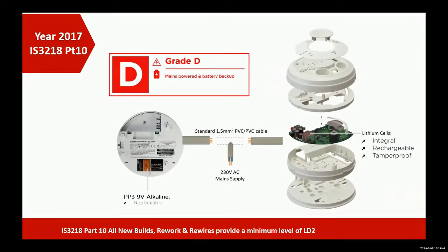So again, going back, we didn't change anything on the grade of system. The grade would still remain mains powered with battery backup. Now the battery backup on the smoke detectors can be either the alkaline replaceable battery backup, which is the PP3 9-volt unit, or it can be the rechargeable lithium cells. And the rechargeable lithium cells are mounted on the PC board. It's a sealed unit. It can't be taken in or out of the unit for any other purpose. So it's a more secure device, I suppose, in relation to getting units on the ceiling and keeping them there, without the batteries being taken out for use in remote controls for kids' toys or TVs or whatever the situation is. So they're the two types of battery backup.